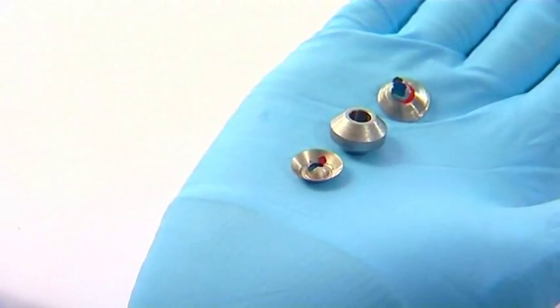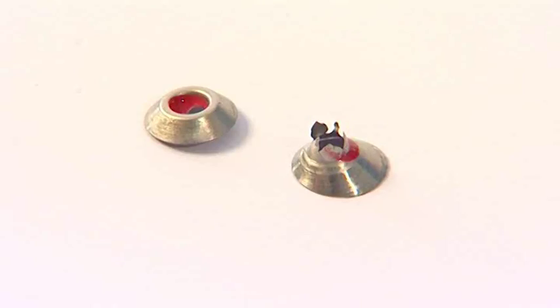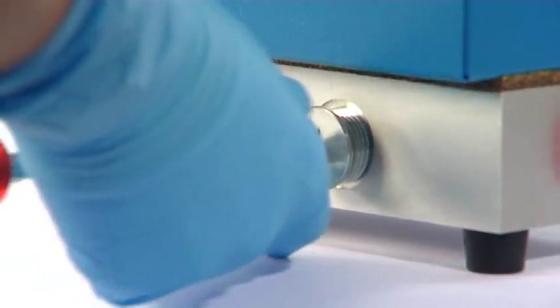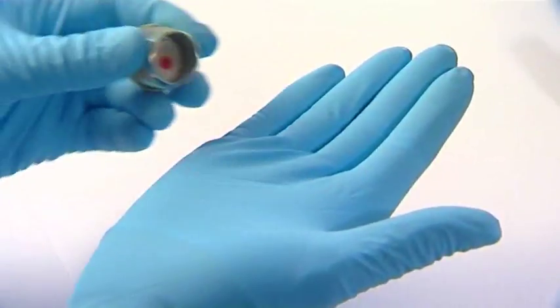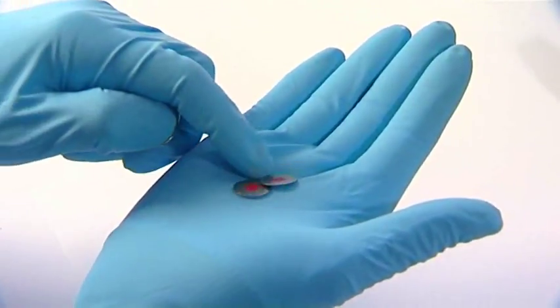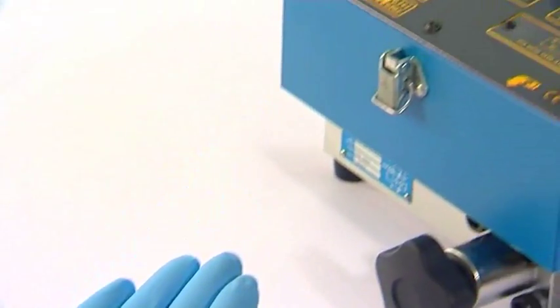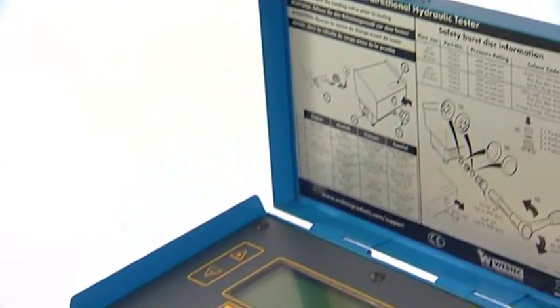Dispose of the disks according to local regulations. Take two new safety burst disks from the spare disk holder and check that they are the correct diameter and pressure rating, which is indicated by their color, against the instruction label.